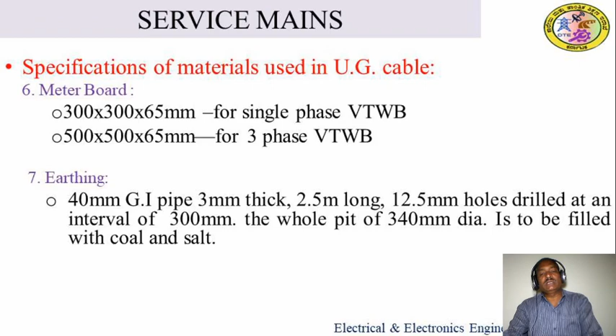Next, come to the earthing. Earthing pipe: the dimensions are 40 mm GI pipe, 3 mm thickness, 2.5 meter long, with 12.5 mm holes drilled at an interval of 300 mm. The pit of 340 mm diameter is to be filled with coal and salt. So this is the dimension of the underground service system.